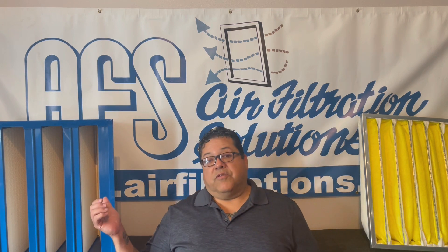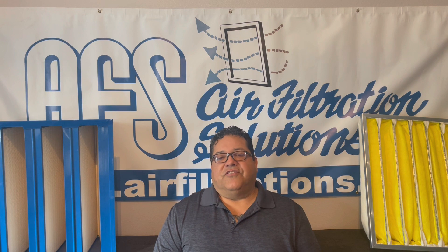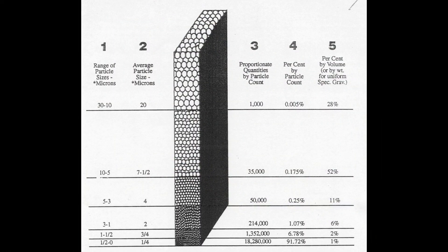Now, this is a MERV 14 and this one's a MERV 16. Is there a huge advantage to having a MERV 16? In my professional opinion, there is not, and I'll show you why. Here's a chart I've shared on this platform before — it's the results of a test report that one of the big players conducted years ago. This pretty much says it all. It supports what I have always said to end users: the majority of particles in the air we're breathing is due to human activity.